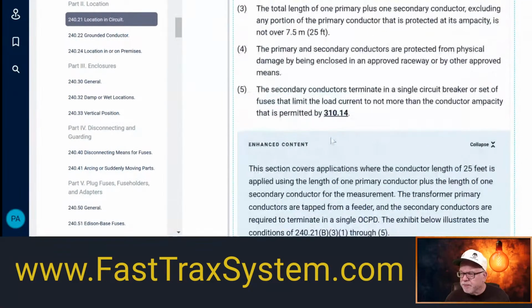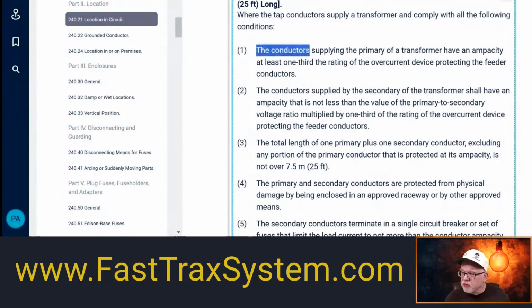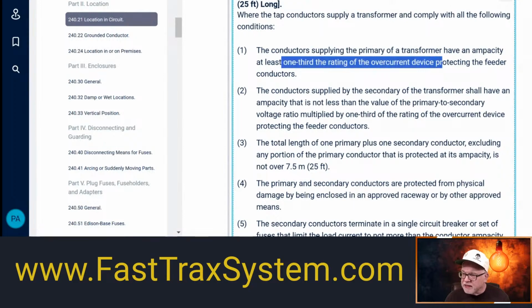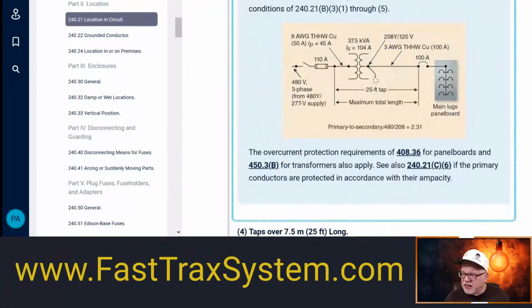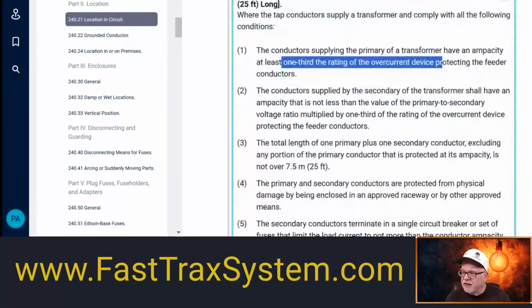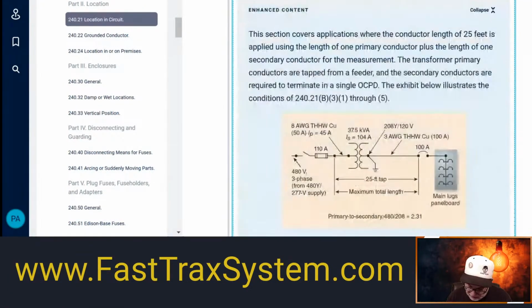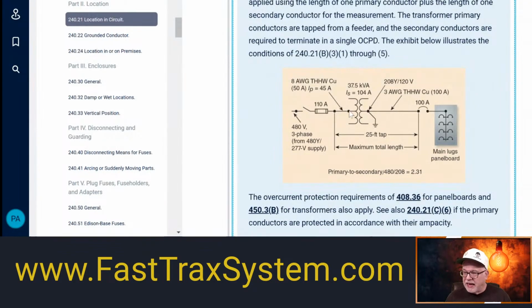What about this primary? All right. The conductor supplying the primary of the transformer has to have an ampacity of at least 1/3 of the rating of the overcurrent protecting the feeder. Okay. So let's see if this 8 is okay. All right. So 8 copper, 50 amps. 110 amps was the primary, and it says that it has to be at least 1/3 of the rating. So we already did this, so 1/3 is 36 amps. So that conductor is at least 1/3 of what? The primary protection. So this 8 gauge is perfectly fine.